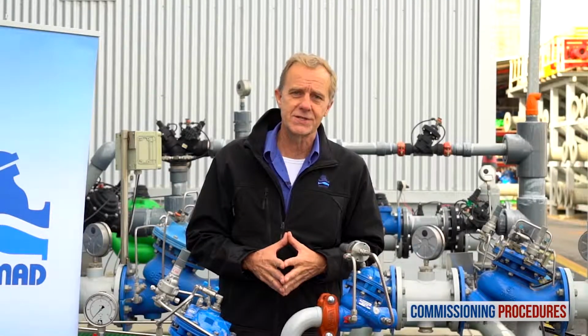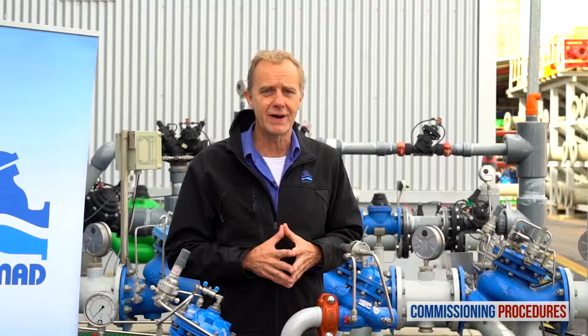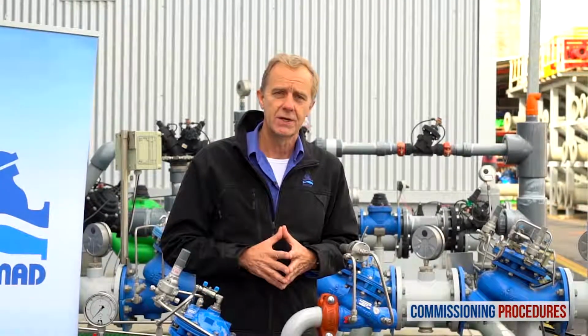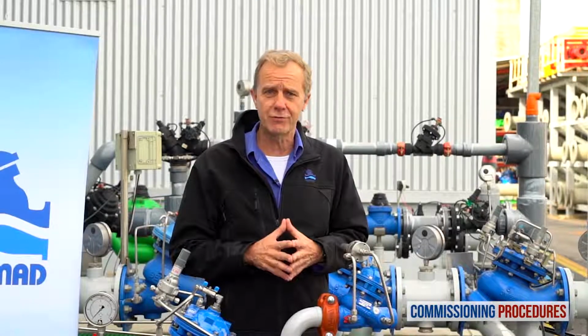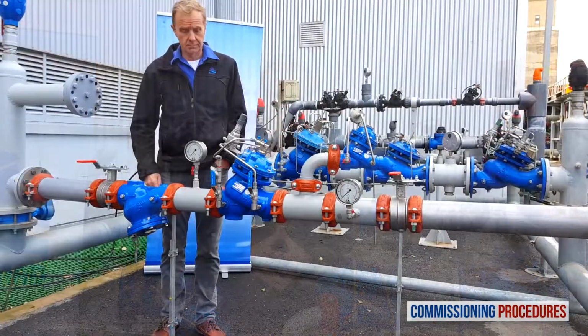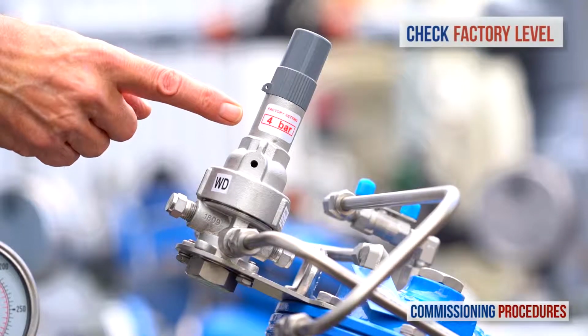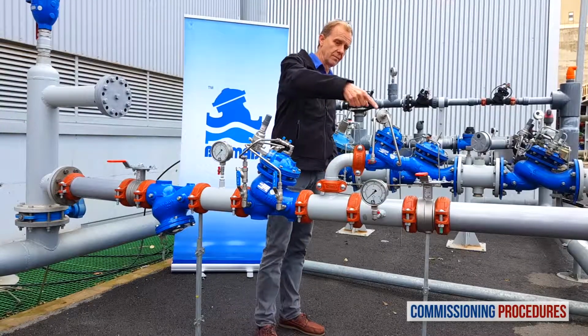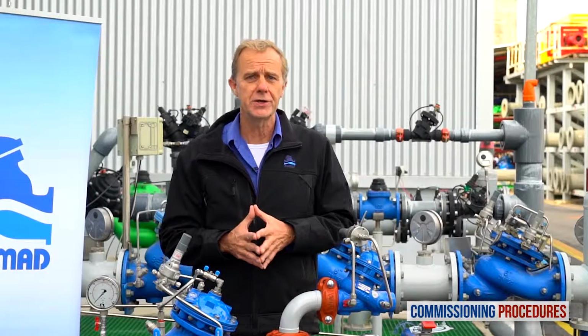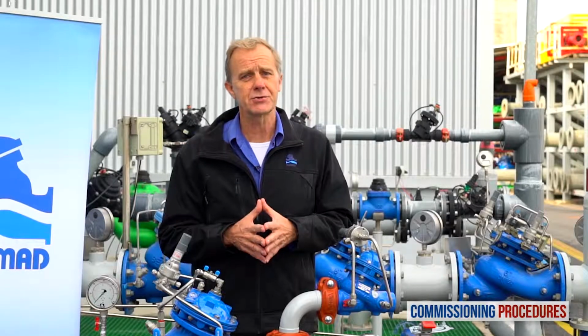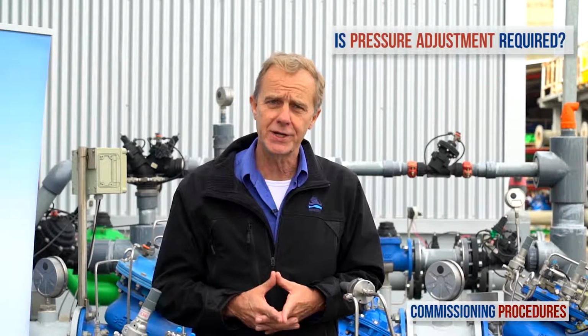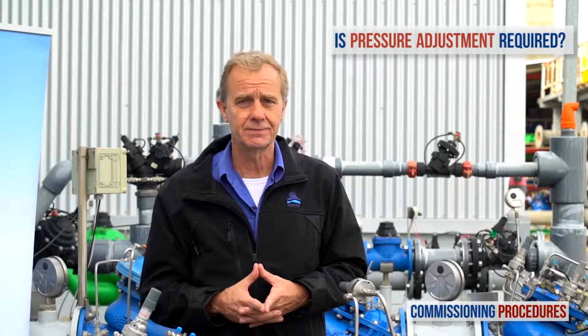Note the pilot levels of the pressure reducing valve and the relief valve are both set at the factory. You can check the factory pilot levels by reading the label on both pilot covers. Here's the label on the pressure reducing valve, and here's the label on the relief valve. Before introducing flow to the station, you need to make sure that the preset pressure levels are compatible with your downstream pressure requirements. If this is the case, you're fine. Otherwise, you will need to adjust the pilots to the required level.